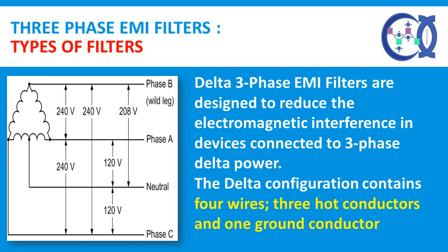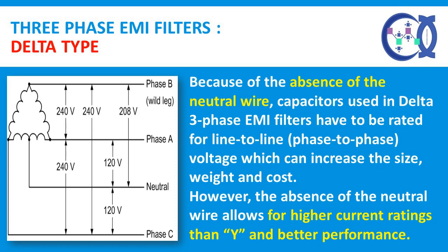Different Types of EMI Filters — Delta Three-Phase EMI Filter: Delta three-phase EMI filters are designed to reduce electromagnetic interference in devices connected to three-phase delta power. The delta configuration contains four wires — three hot conductors and one ground conductor. Because of the absence of the neutral wire, capacitors used in delta three-phase EMI filters have to be rated for line-to-line, phase-to-phase voltage, which can increase the size, weight, and cost. However, the absence of the neutral wire allows for higher current ratings than Y and better performance in the same given cubic volume.